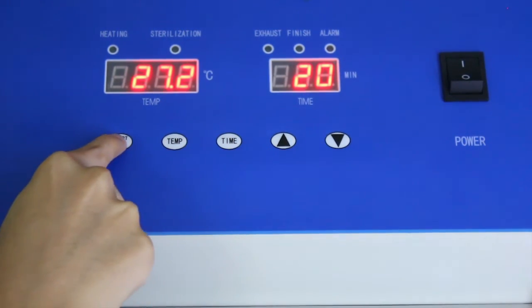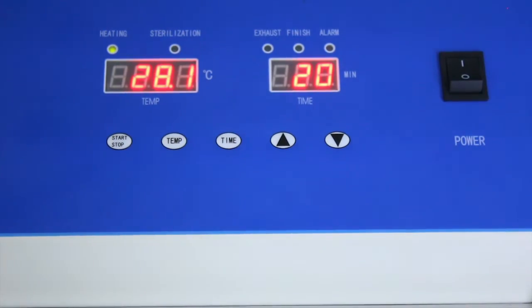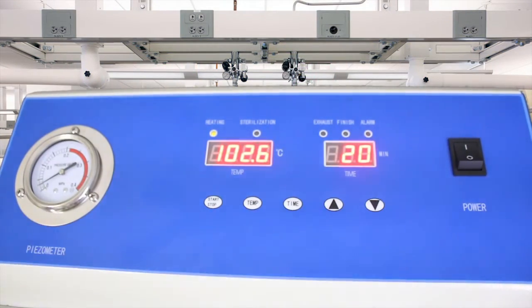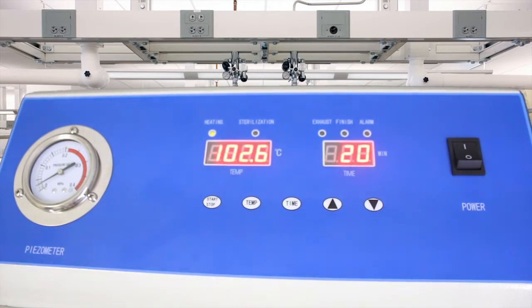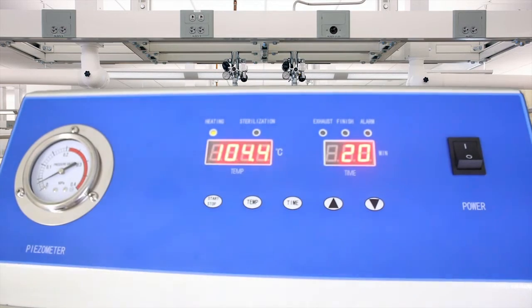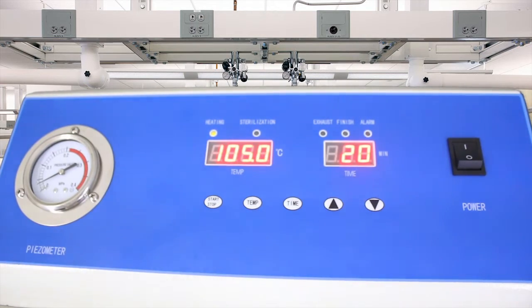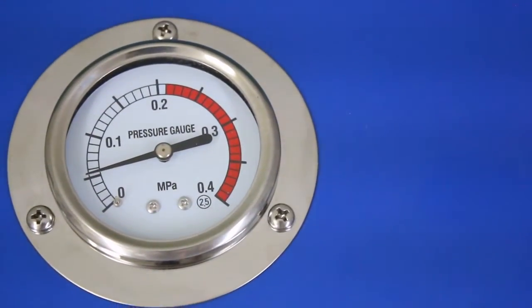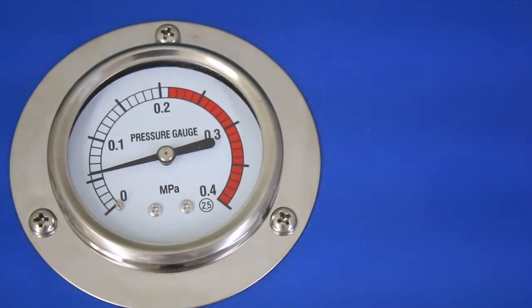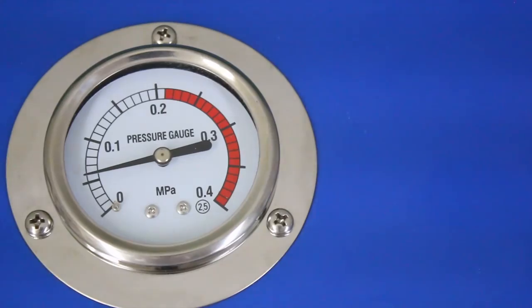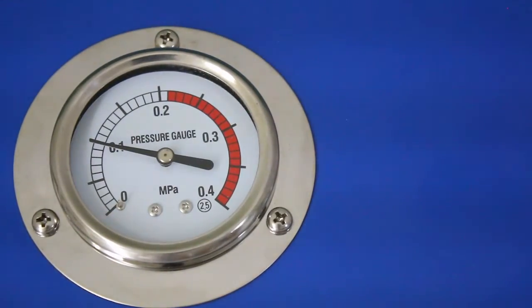Press Start on the control panel. The temperature will start to rise. When it reaches 105 degrees centigrade, the steam release valve will close and you will hear a clicking sound. Likewise, the pressure will increase until it reaches 0.15 megapascals at 121 degrees centigrade. At this point, the sterilization time will begin to count down.